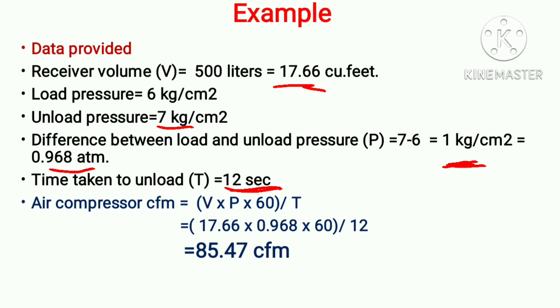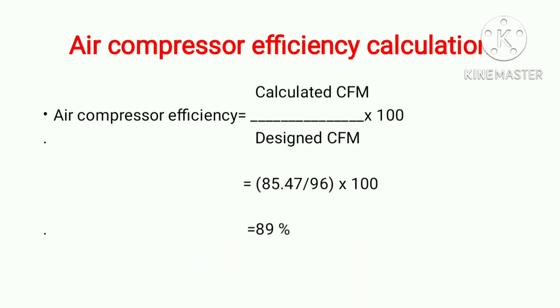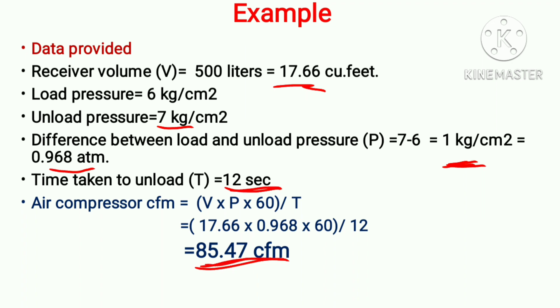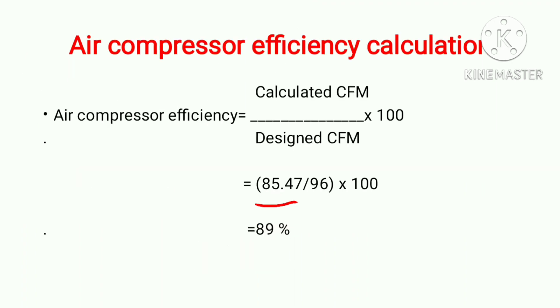Putting all values into the formula, the actual calculated CFM of the air compressor is 85.47 CFM. Now for volumetric efficiency: the formula is calculated CFM divided by designed CFM, multiplied by 100. Our calculated CFM is 85.47 and the designed CFM from the nameplate is 96. After calculation, we get 89%.